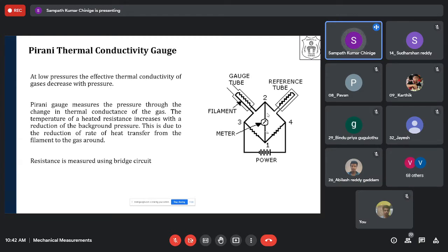Okay, so that is the basic measurement process that we follow for vacuum pressure measurement in a Pirani thermal conductivity gauge. The question here is, sir, that is true, but how can we eliminate the temperature? It may be due to temperature also. Maybe at low pressure, the temperature may be a little bit higher. So because of the temperature, again, the thermal conductivity of our gas is varying. So how do you ensure that both are being taken care of?